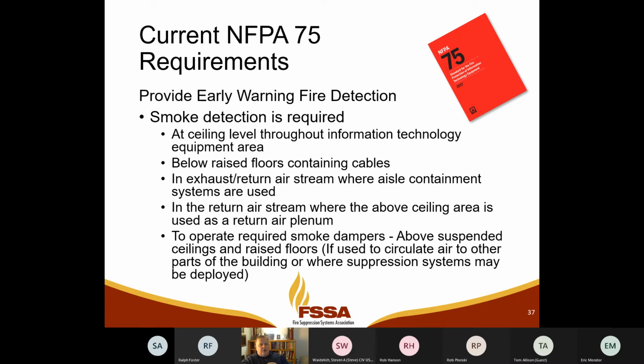Fourth point, in the return air stream, where the above ceiling area is used as a return air plenum, you should have smoke detection. So basically, if we're taking air up above a suspended ceiling to use it as a plenum to get it back to the air handling equipment, then we need to have smoke detection up there. So that's where it's suggesting it.